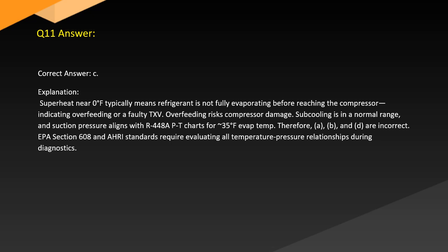Answer. Correct answer: C. Explanation: Superheat near 0 degrees typically means refrigerant is not fully evaporating before reaching the compressor, indicating overfeeding, or a faulty TXV. Overfeeding risks compressor damage. Subcooling is in normal range, and suction pressure aligns with R448A. The PT chart for 35 degree evap temp. Therefore A, B, and D are incorrect. EPA Section 608 and RSES standards require evaluating all temperature-pressure relationships during diagnostics.